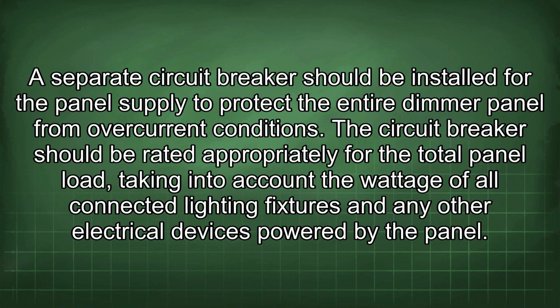A separate circuit breaker should be installed for the panel supply to protect the entire dimmer panel from overcurrent conditions. The circuit breaker should be rated appropriately for the total panel load, taking into account the wattage of all connected lighting fixtures and any other electrical devices powered by the panel.